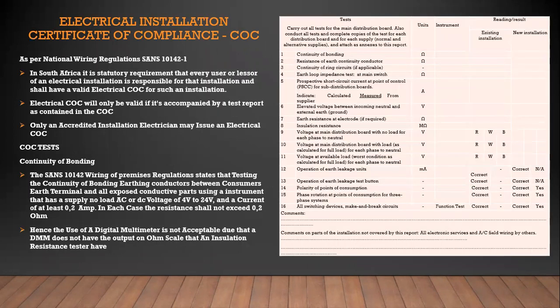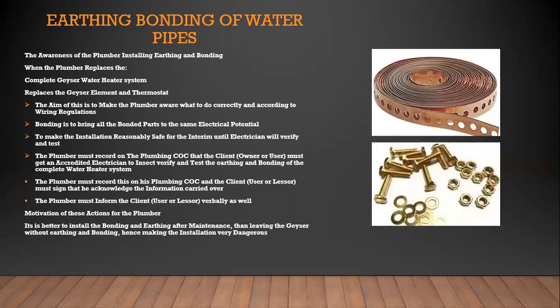We're looking at the electrical installation certificate, the COC. There you can just get an idea of all the tests that need to be conducted in a COC. And the first one there, that's the important one, the continuity of bonding for your geyser, which stipulates 0.2 ohm and how to test it. You must test the continuity of the bonding conductor with an insulation resistance tester and not a normal multimeter. That clearly is stipulated by the regulations.